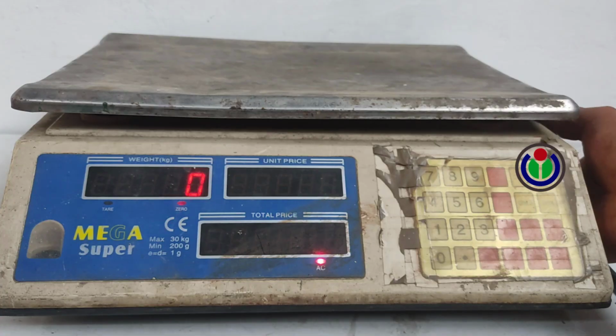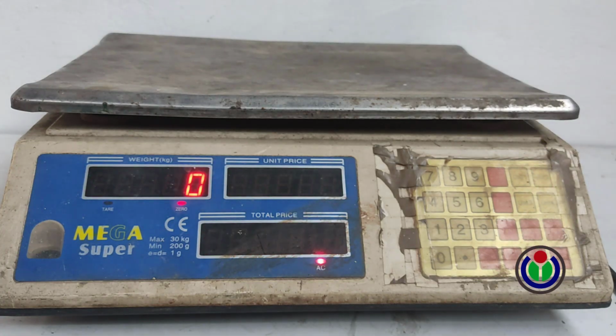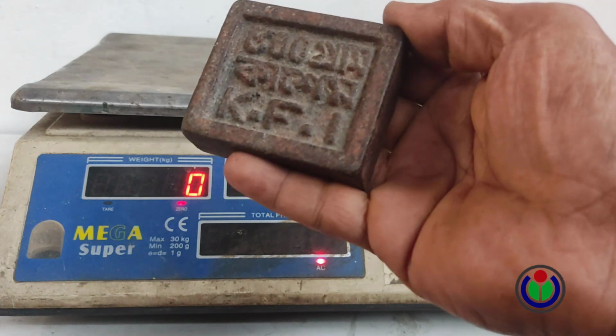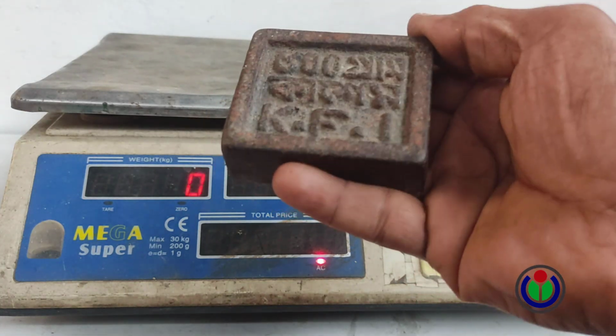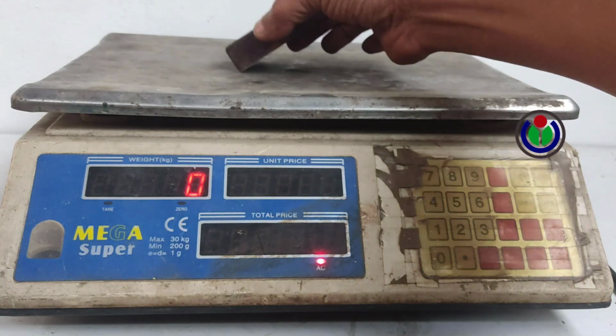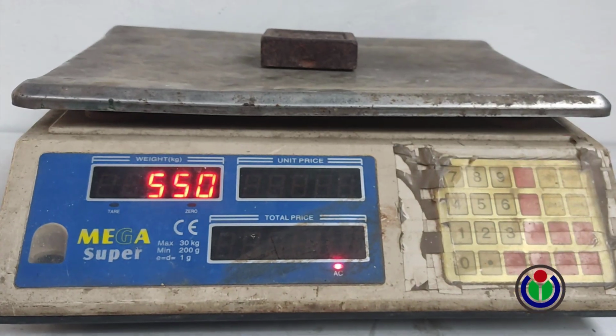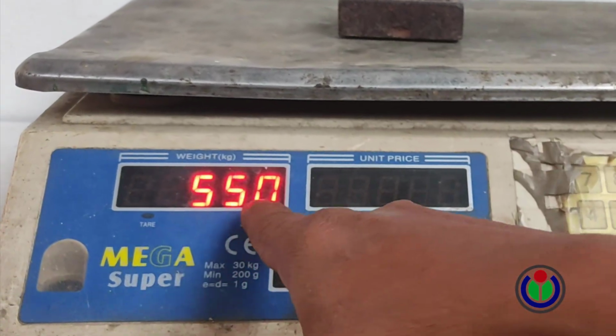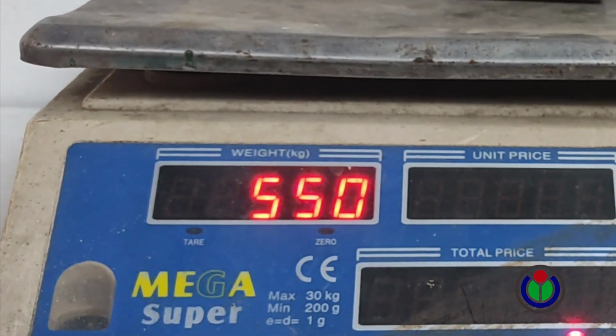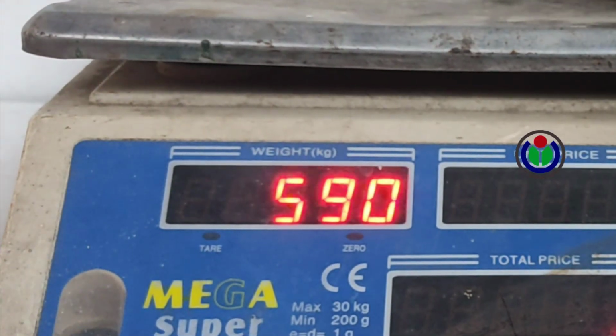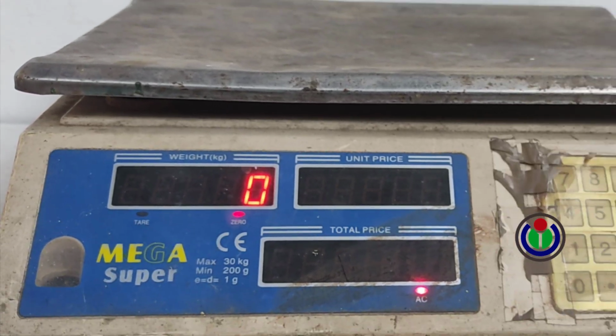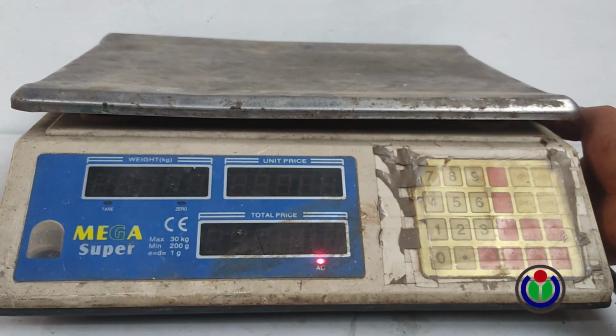To solve this problem, first you need to get a standard calibration weight set. Then turn on the machine and see the weight measurement information of the weight set. The actual weight of the weight set is 500 grams, but it is displaying 550 grams, more than its actual weight, which is 50 grams more. So now I will calibrate this digital scale.